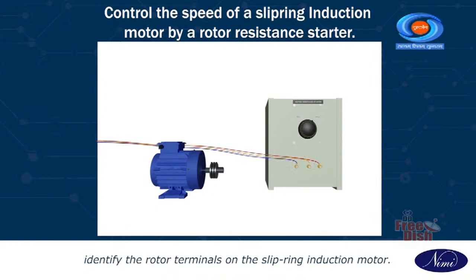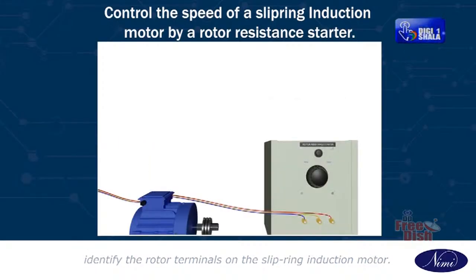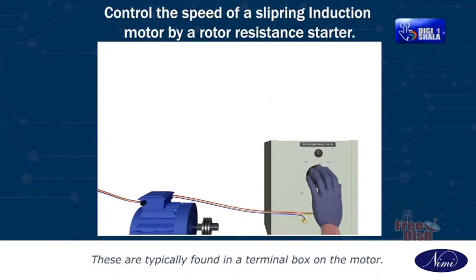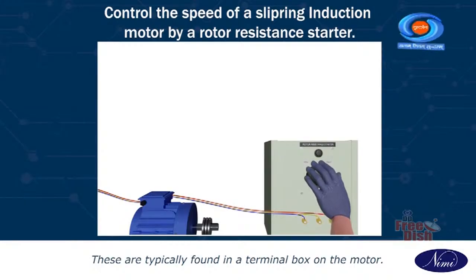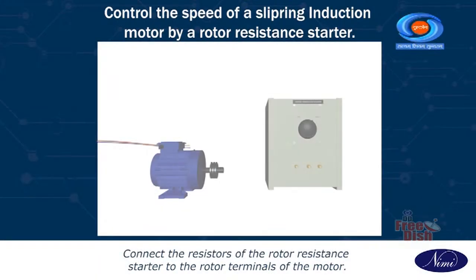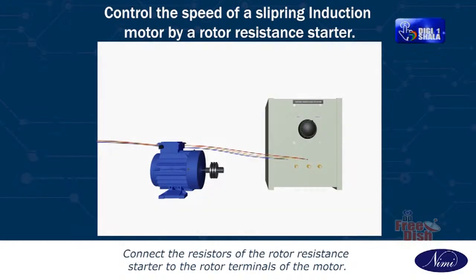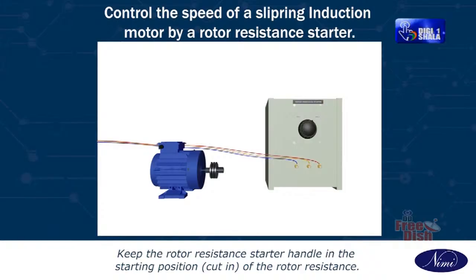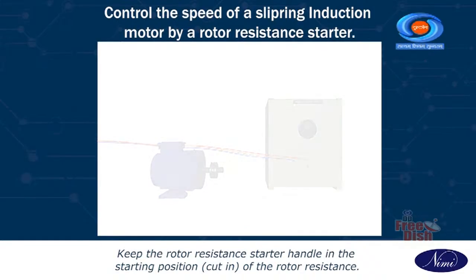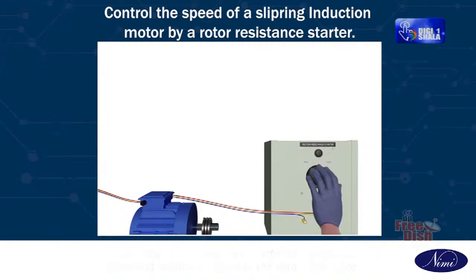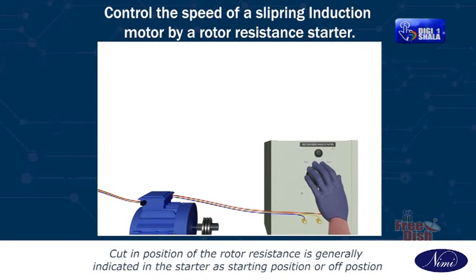Identify the rotor terminals on the slip ring induction motor. These are typically found in a terminal box on the motor. Connect the resistors of the rotor resistance starter to the rotor terminals of the motor. Keep the rotor resistance starter handle in the starting position. Cut-in of the rotor resistance. Cut-in position of the rotor resistance is generally indicated in the starter as starting position or off position.